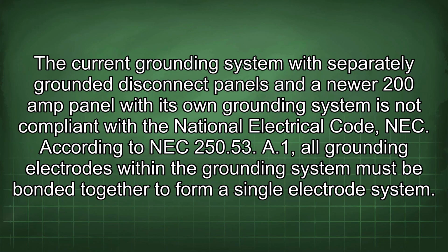The current grounding system, with separately grounded disconnect panels and a newer 200 amp panel with its own grounding system, is not compliant with the National Electrical Code (NEC). According to NEC 250.53 A1, all grounding electrodes within the grounding system must be bonded together to form a single electrode system.